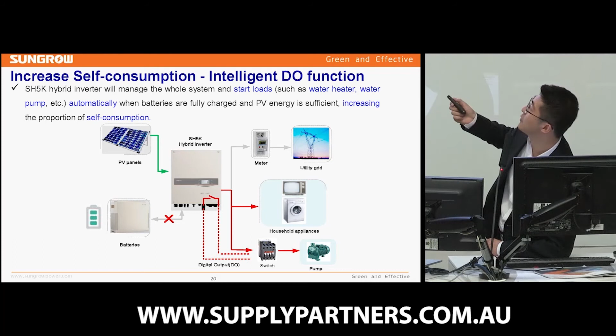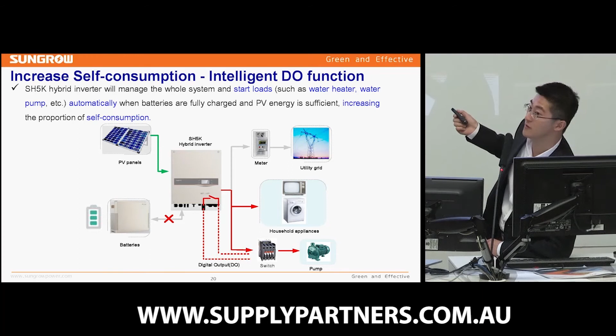There are 3 modes to activate this digital output. The first one is on and off mode. Basically, it can turn on and turn off to activate this digital output. The second one is the customer can set the time, the beginning and ending time, during which it can turn on the load. The third one is the optimize mode. So basically, the customer can set the value using this LCD display. When the energy meter measures the power, if the power is more than the setting value, the digital output will activate and control the load.